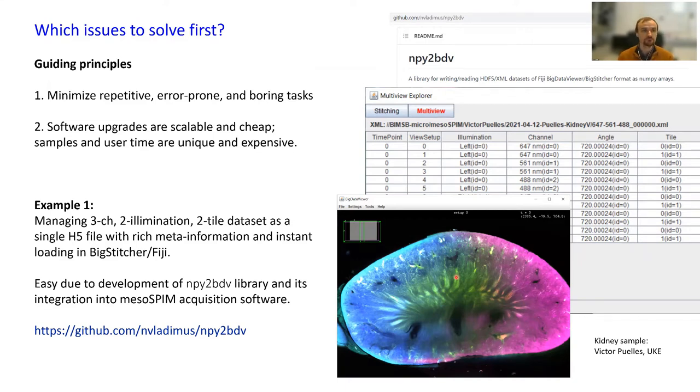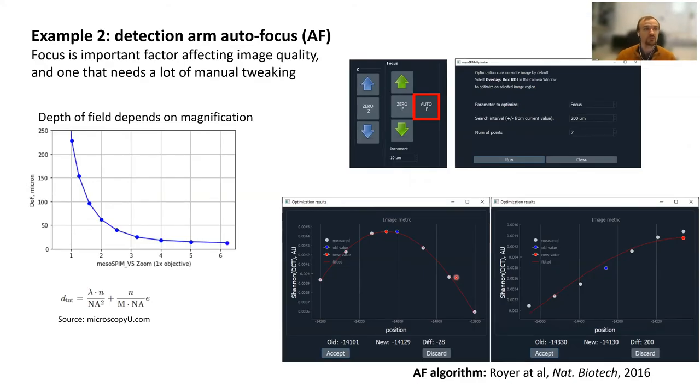Another recent development in the software is addition of autofocus, which I demonstrated in the hands-on session. Focus is probably one of the most important factors affecting image quality. In mesoSPIM particularly, this requires usually quite a lot of manual tweaking. Every time you change magnification, you need to adjust your focus. Depth of field depends very strongly on magnification. At zoom 1x, if you use a standard formula, the depth of field is almost 250 microns, but at zoom 6x it is only about 15 microns.